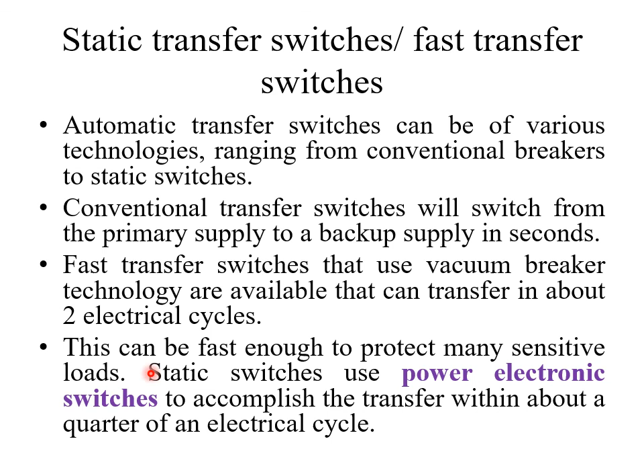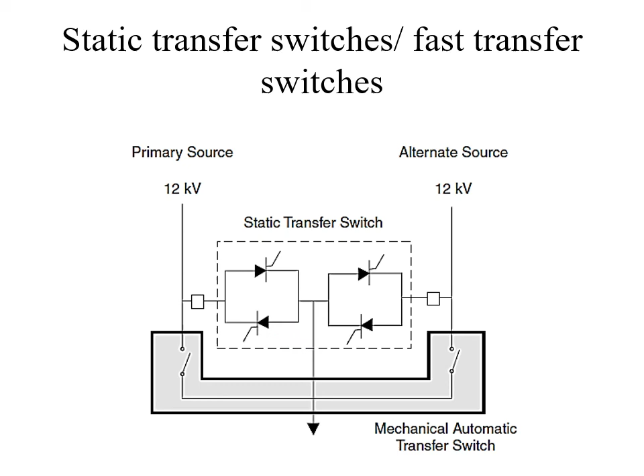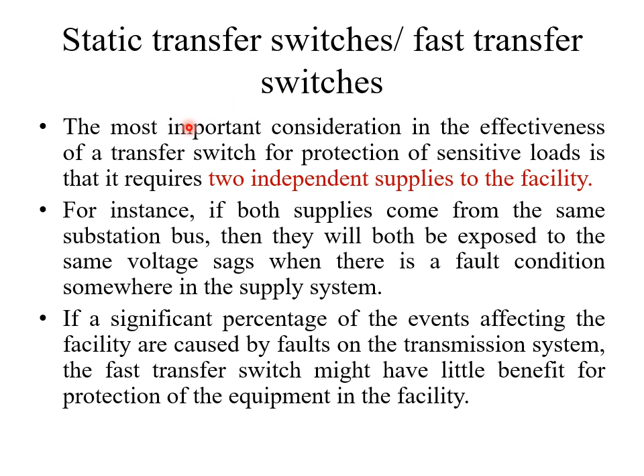This is the diagrammatic representation of a static or fast transfer switch. You see the 12 kV primary source and the 12 kV alternate source, and this static transfer switch can operate very fast to do this transition, compared to the mechanical or conventional transfer switch. The important consideration to make use of this static or fast transfer switch is the availability of power supply. At least 2 independent power supplies are required to enable the transfer switches to operate.